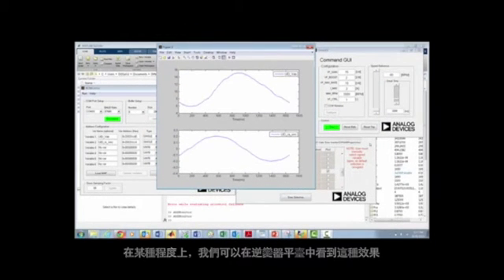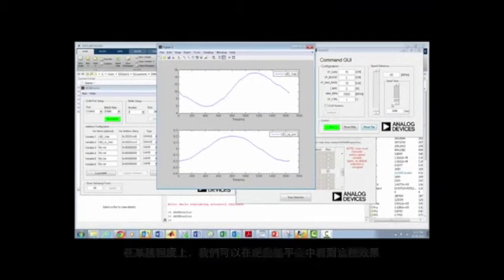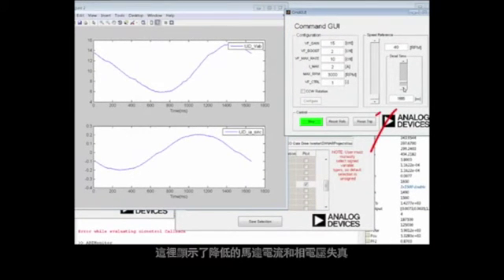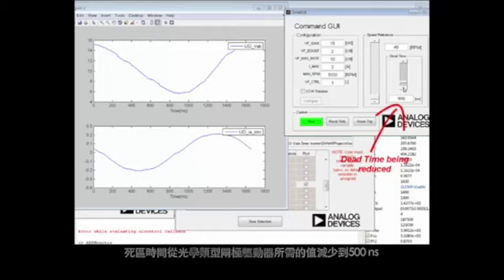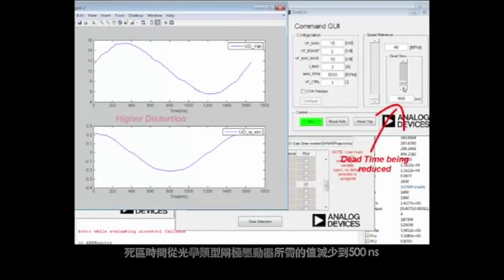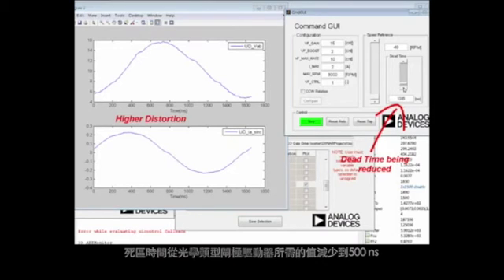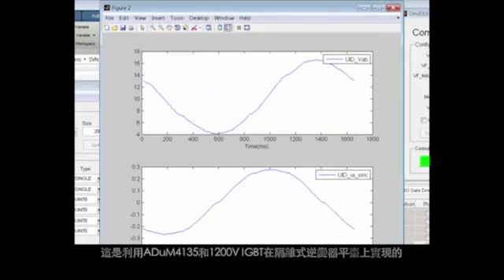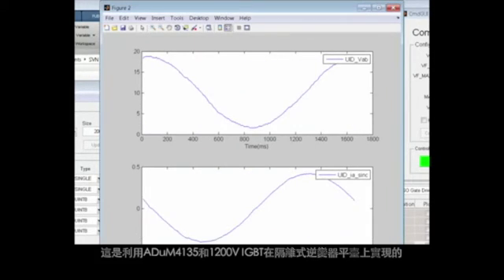We can see this effect to some extent in the inverter platform. Here we show the reduced motor current and phase voltage distortion when the dead time is reduced from the values required by optocoupler type gate drivers to the 500 nanoseconds achievable using the ADUM4135 in conjunction with the 1200 volt IGBTs on the isolated inverted platform.